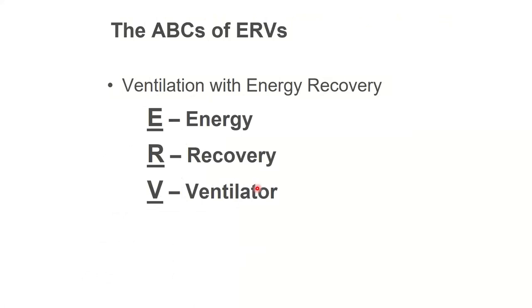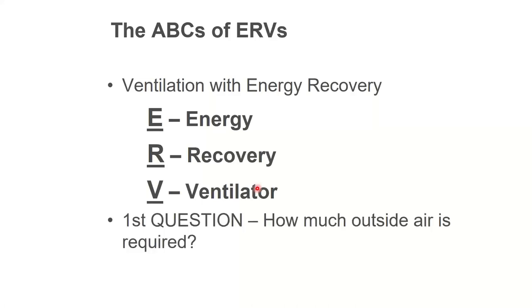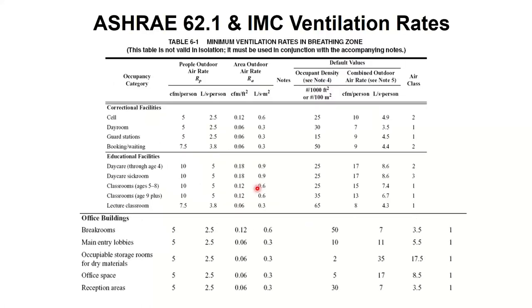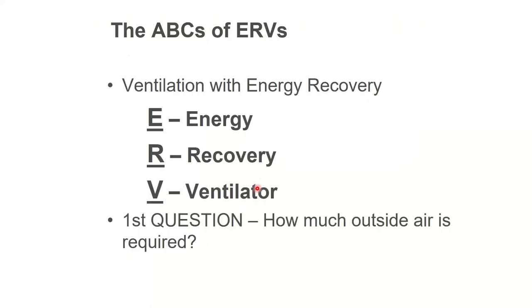All right, so where does the ERV come into the discussion? ERV, if you didn't know, stands for Energy Recovery Ventilator. First thing I always ask is how much outside air was required. So basically, what did this table tell you to do? If that table told you that your building needs 100 CFM, this is not an interesting project for an ERV. 100 CFM is statistically zero. It's basically nothing. You have an unoccupied building with one person in it, right? Who cares? The more outside air you have, the more interesting it gets.